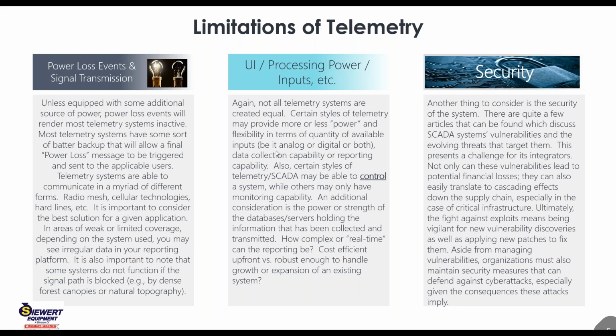Something simple in telemetry typically requires power. So if the equipment you're monitoring loses power, that's going to be an interruption in data transmission — you'll lose the ability to see that equipment remotely. Some telemetry and SCADA systems come with a battery backup, but don't think that backup is capable of running the piece of equipment. Generally what it does is allow the monitoring device to send out a single message — power loss, power failure, power interruption — to trigger you to know that you've lost your voltage source to this equipment.